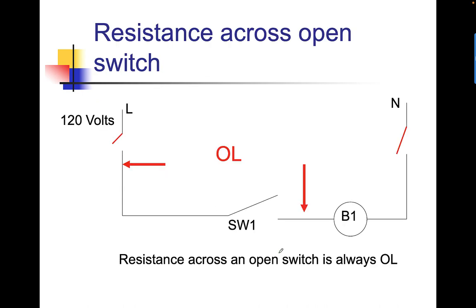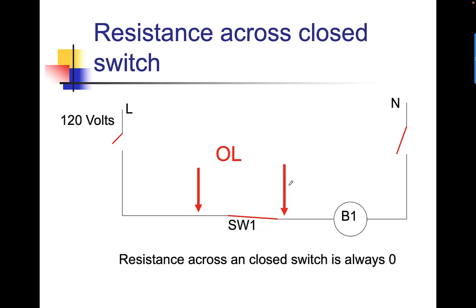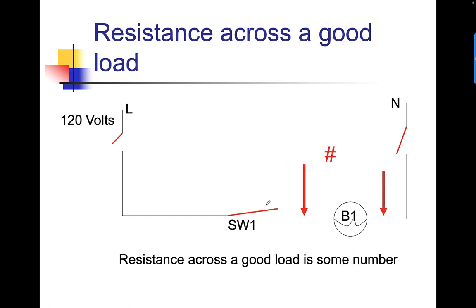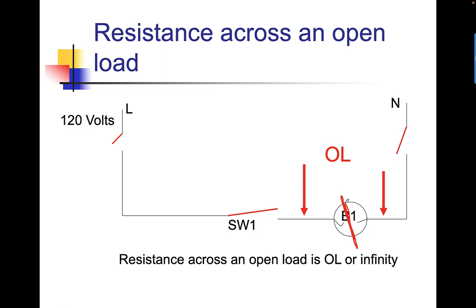Resistance across an open switch is going to show OL or infinite — there's no way for any current to pass across that open switch. Resistance across a closed switch is always going to be zero. Resistance across a good load is going to be some number. Resistance across an open load is going to be OL or infinite.